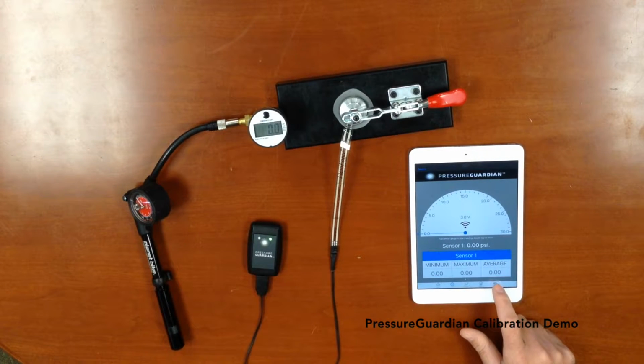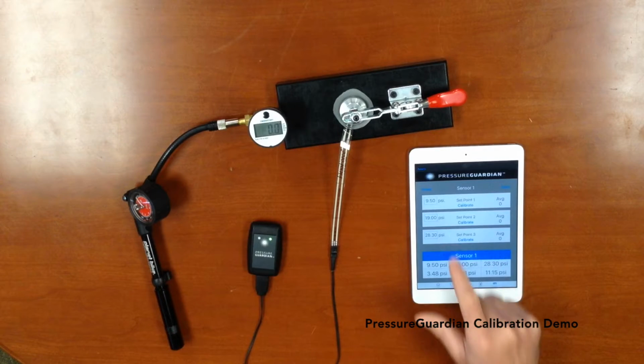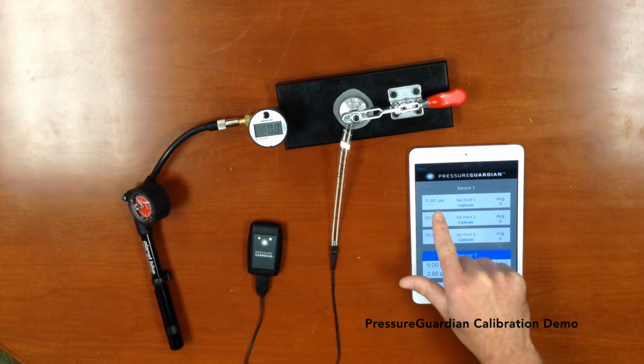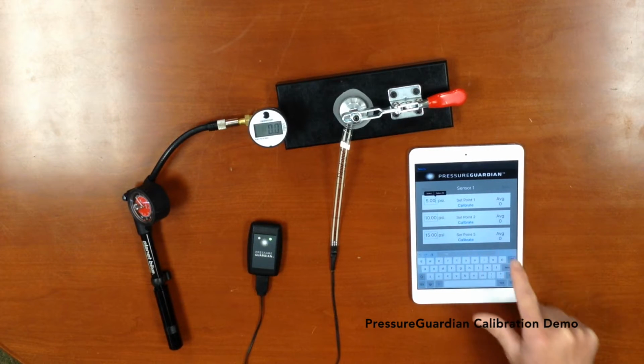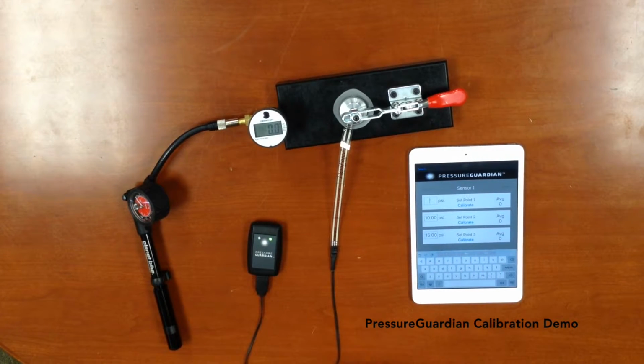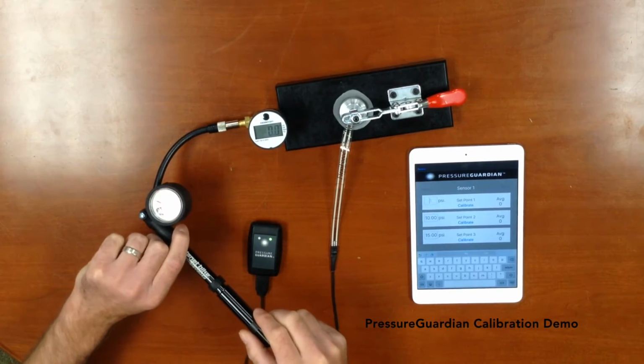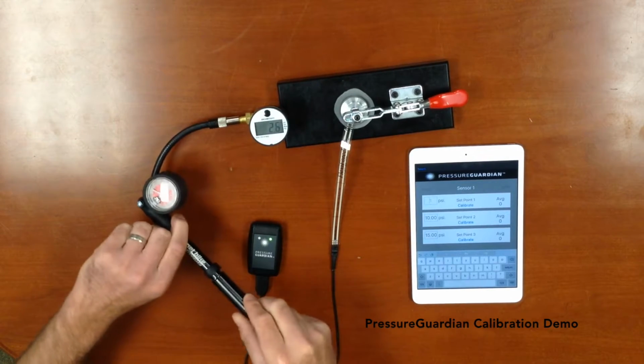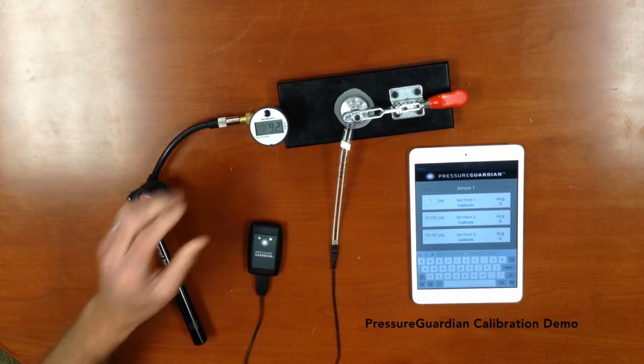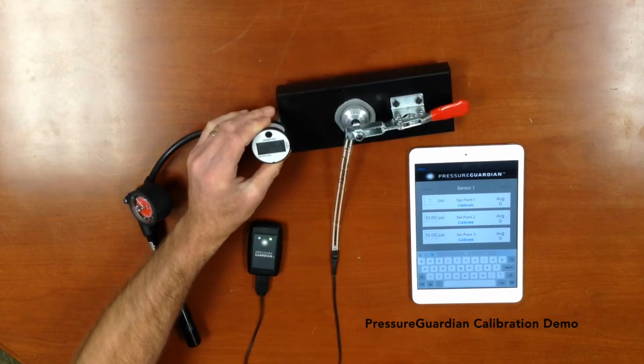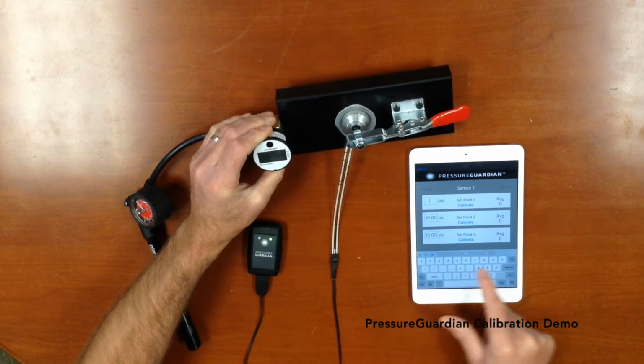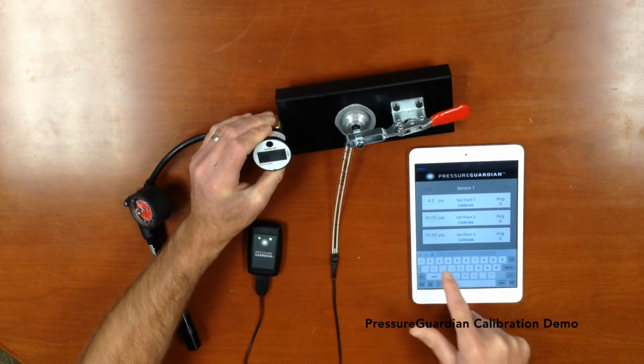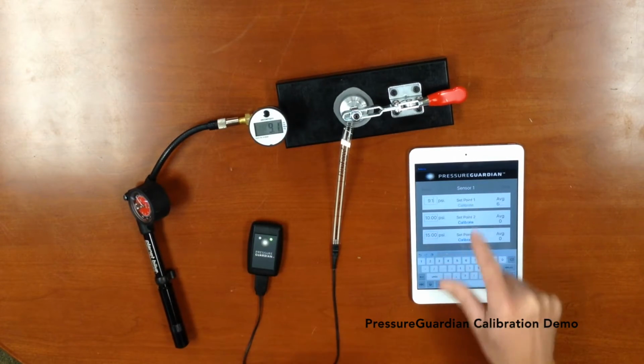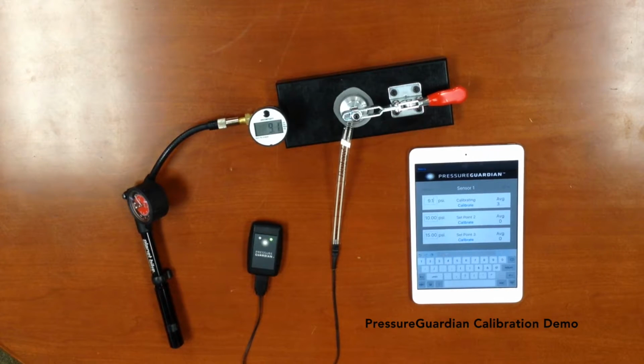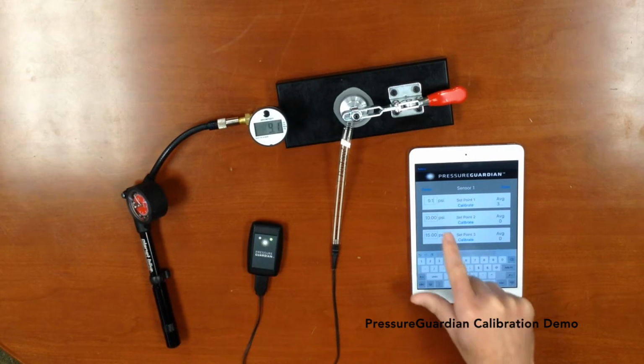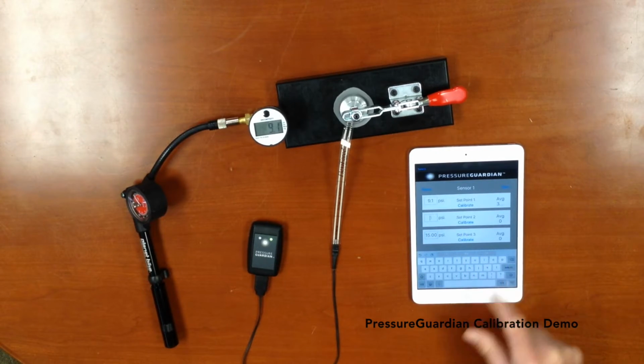Now we're ready to calibrate, so we're going to click on the calibration tab. I'm going to hit reset. I'm going to go into my first set point. We're going to delete the number that is there. Then I'm going to go to my pump. I'm going to give 1 full pump. Now I'm going to read the number on my gauge and enter that number into our box. We're going to hit calibrate, and we're going to wait till this is done calibrating before we go into our second set point.